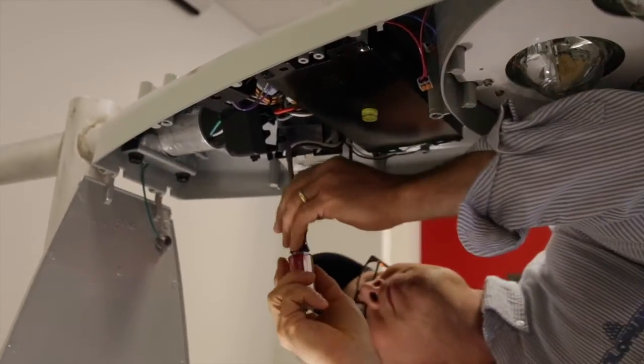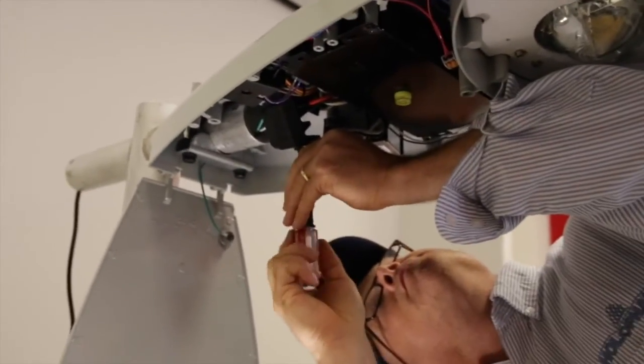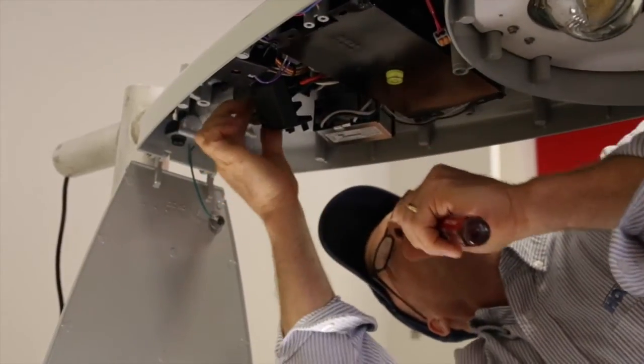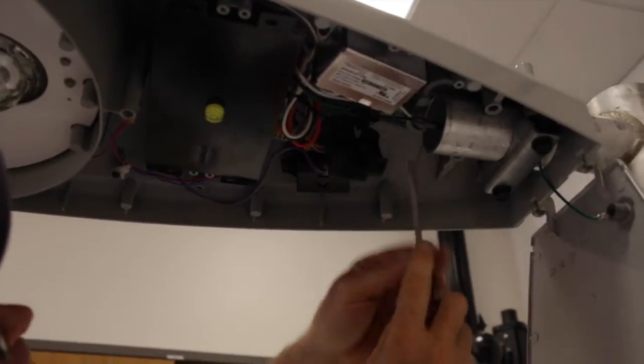Make sure that none of the wires get pinched during installation. Loosen the terminal block screws and install the color-coded wires: line, ground, and common. Tighten the terminal block screws after you install each wire.